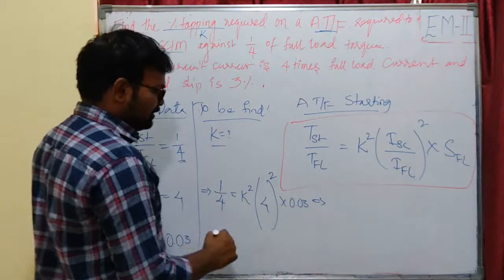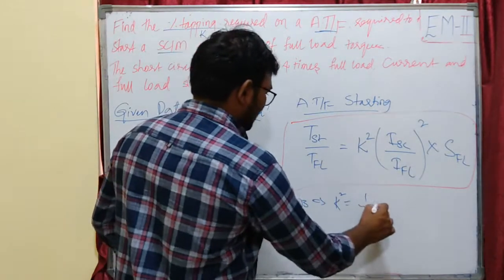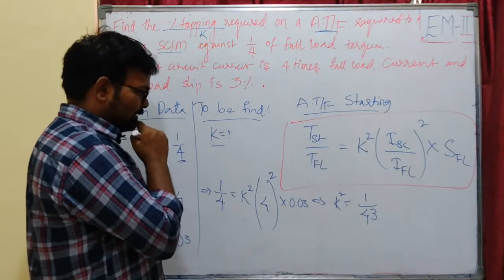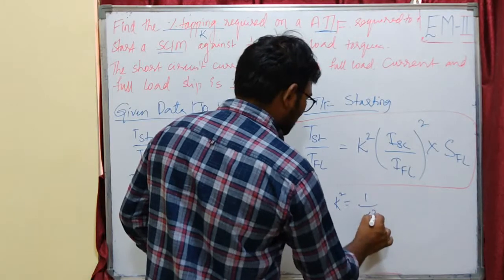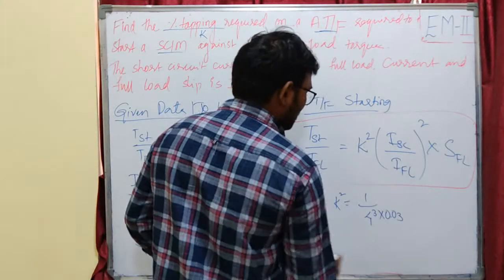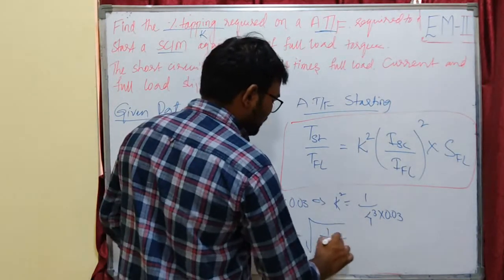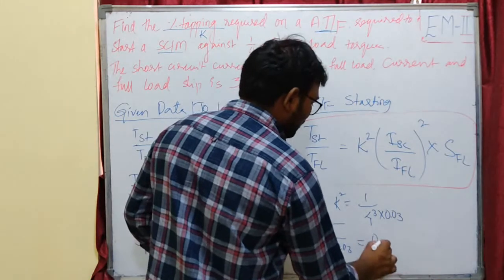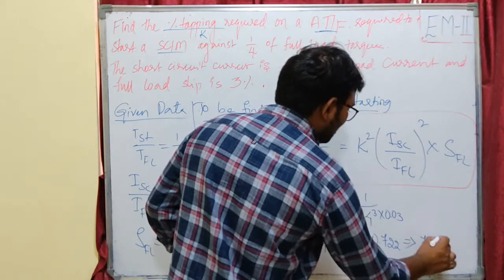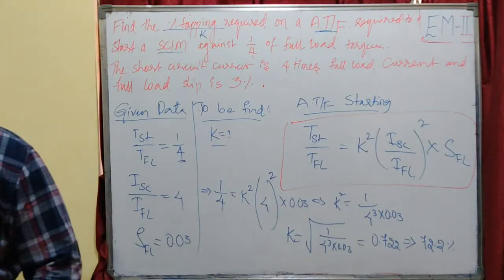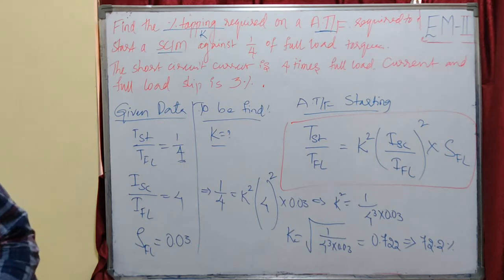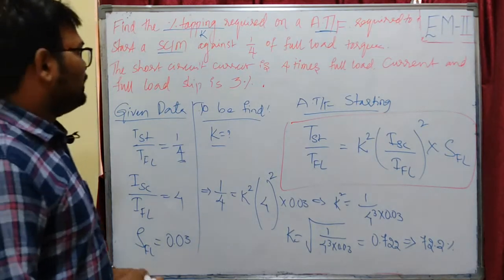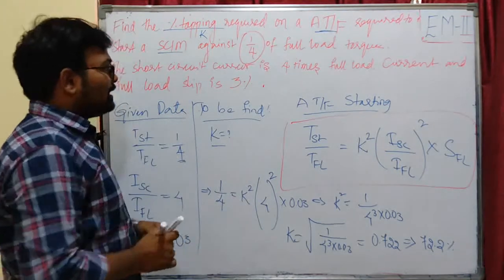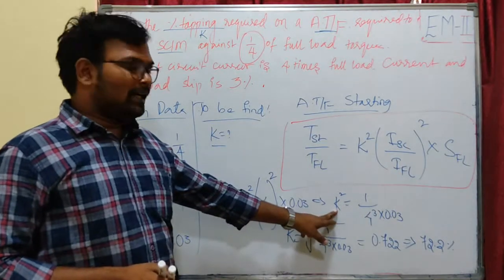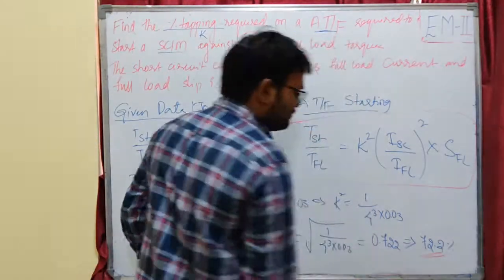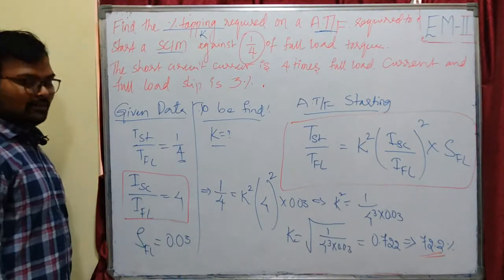So you can find K by shifting: K square equals 1 by 4 cube, if you take the 4 square to the opposite side, into 0.03. If you shift the square root to the other side, this will be 0.722. That means the percentage tapping is 72.2%. So in order to get our starting torque 1 by 4 times full load torque, you will have to switch the auto transformer to 72.2%, and you can limit the starting current to 4 times full load current with slip 0.03.